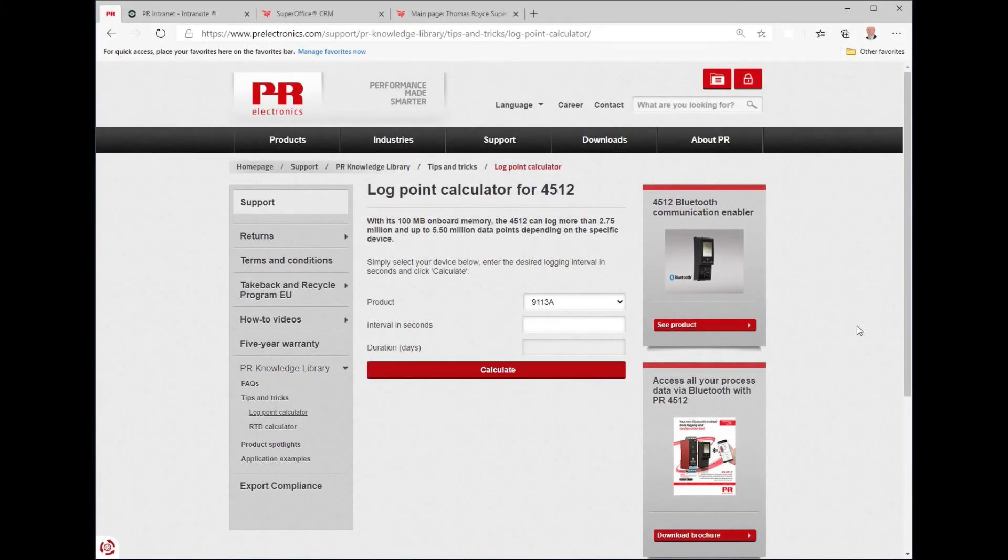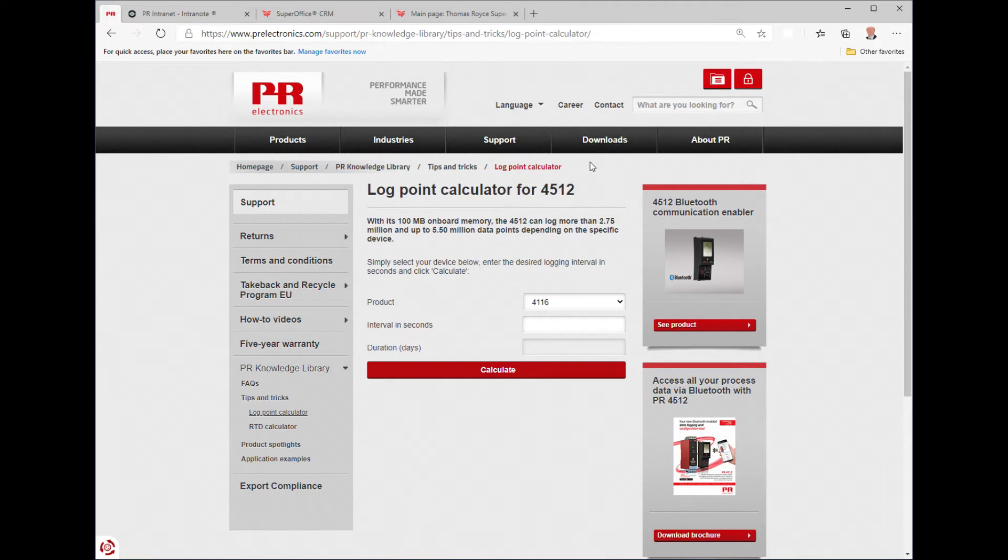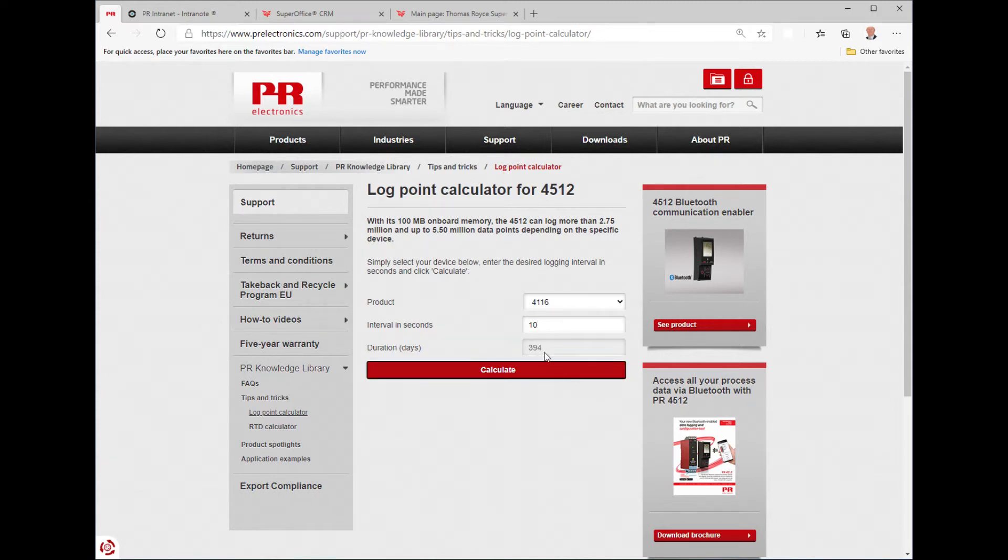A logging calculator is available on our website. Just select the product type and log interval then click calculate to determine how many days of logging is possible. In this example, the 4116 can record a log every 10 seconds for 394 days.